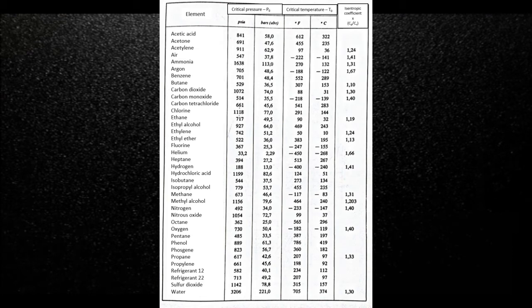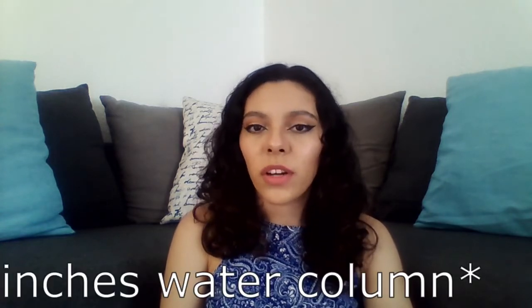In this table, we can see the relationship between the maximum differential pressure that the element can admit with the static pressure in the line and with the graphs of straight pipe lengths and pressure drops. Normally, the flow measurement of liquids are a differential pressure of 2500 mm water column or 100 inches water column.